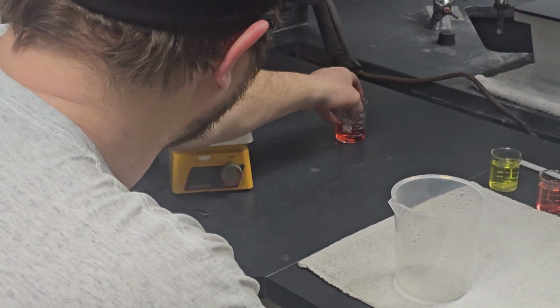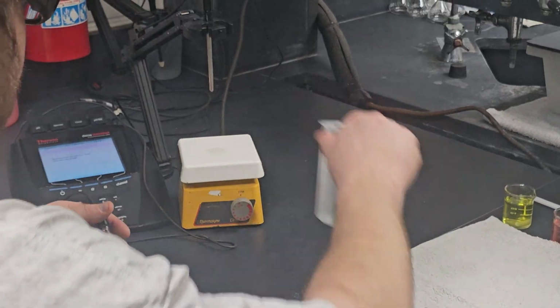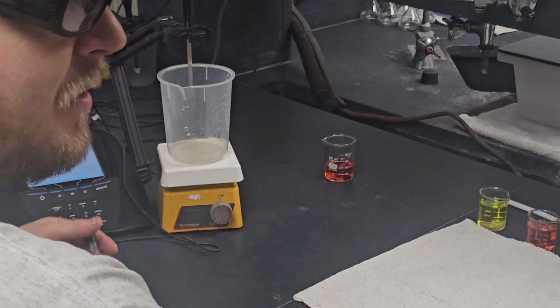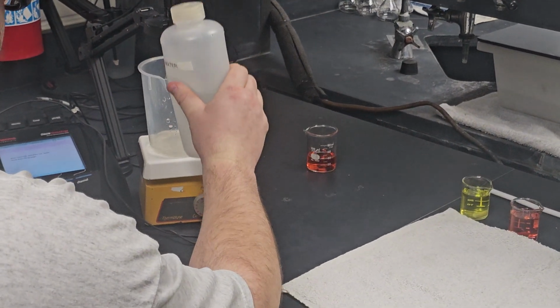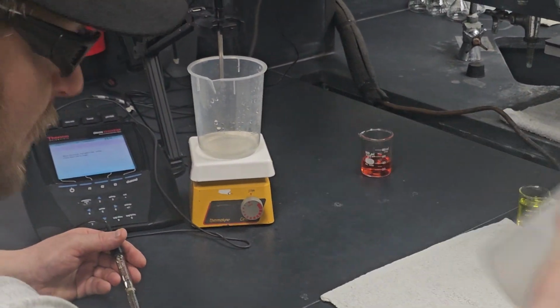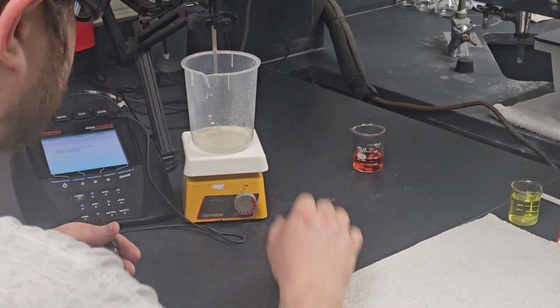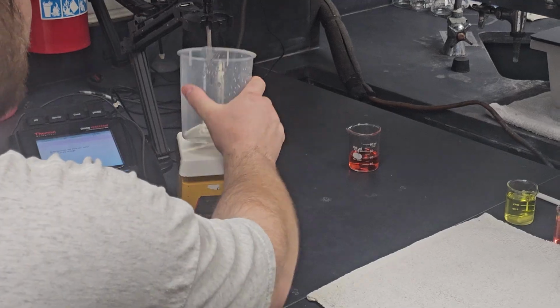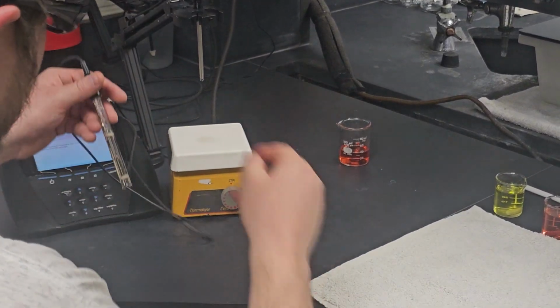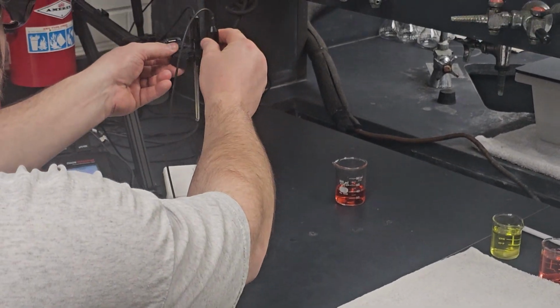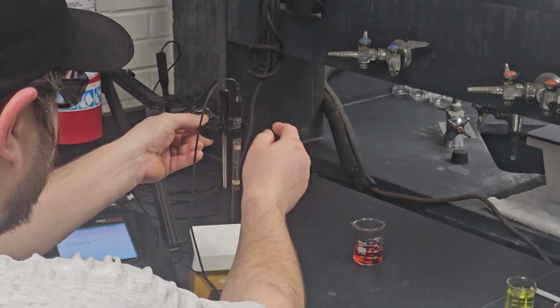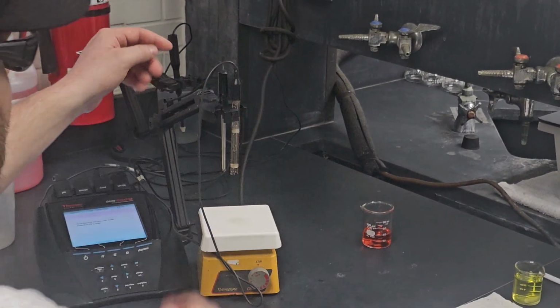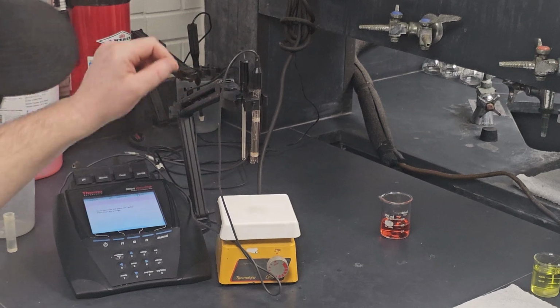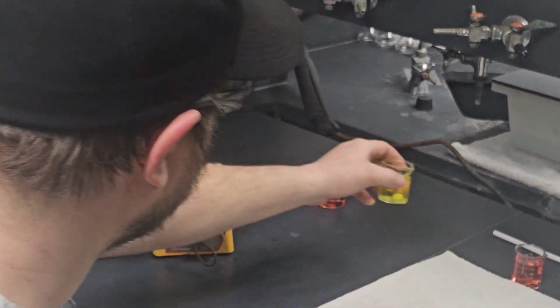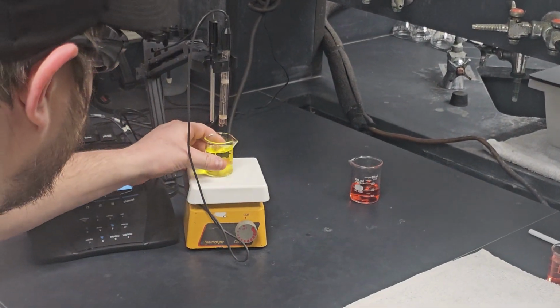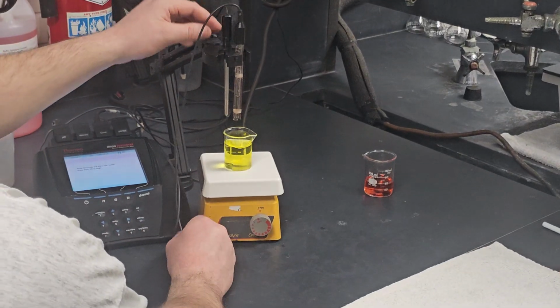Remove the storage fluid from the thermometer. Our pH is associated with a temperature as well. That's why we store it in that expired pH 4 buffer solution, just so that it's reading a consistent temperature. So we've rinsed our probe and our thermometer. We clip the probe into the slot on the arm next to the thermometer, and then we start with our first buffer solution, buffer 7, the yellow.